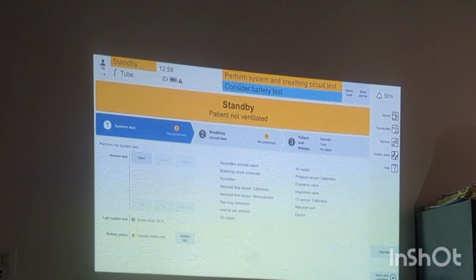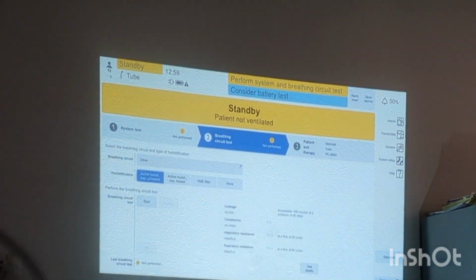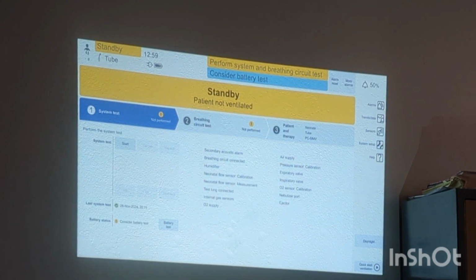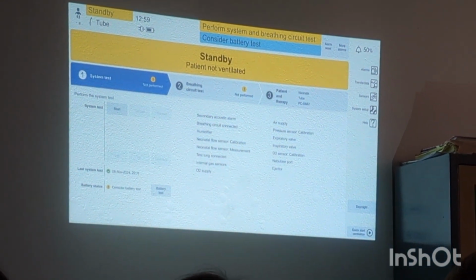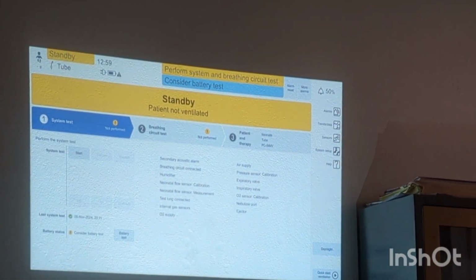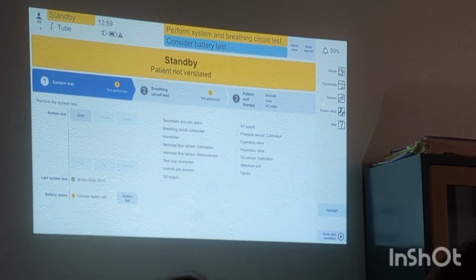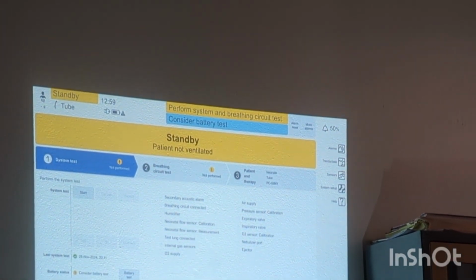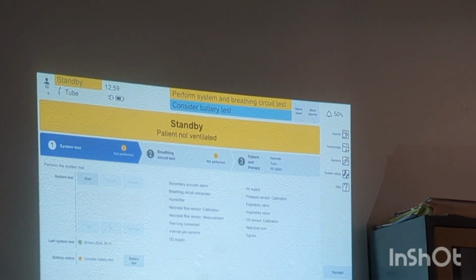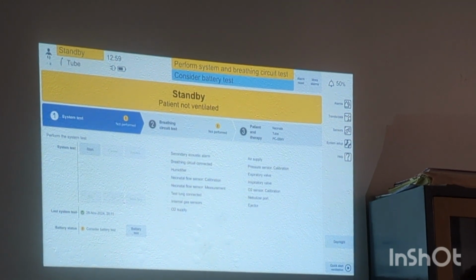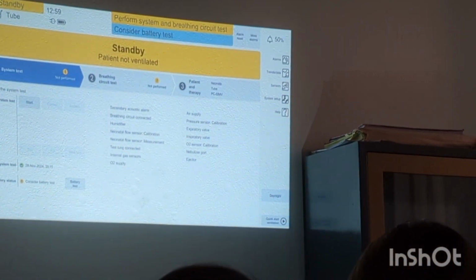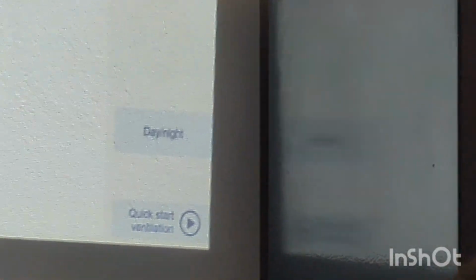So here you can see there are 3-4 tabs. The first tab is for the system test. Here you can see the system test start and what things we are going to perform during the device check. And one more thing, on the right side you can see the quick start ventilation. So in case of emergency, suppose you are in a hurry, the patient has arrived, and you don't have time to do all this device check, you can also quick start the ventilation.